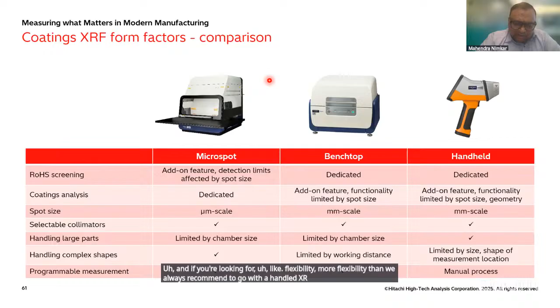So this is our complete range of products. What we covered is basically: if you want to do a typical coating thickness application, we always suggest going with a micro focus or micro spot XRF instrument. If you're going for RoHS or bulk elemental analysis, we recommend a dedicated benchtop XRF. And if you're looking for more flexibility, then we always recommend a handheld XRF. Handheld XRF is also capable of doing coating thickness.